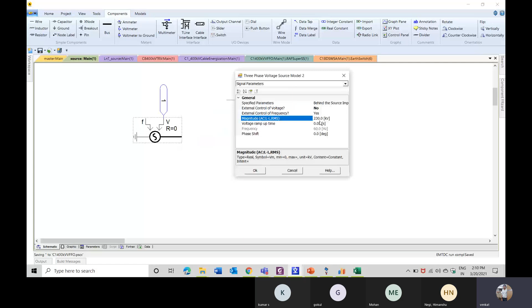Like this, this option varies, and this ramp up time I showed you yesterday. The voltage here is your line to line RMS, which is already your line voltage. For example, if it's 220 kV line or 132 kV, it has mentioned AC line to line RMS, so it is always that. You don't need to change it to another value. For example, you don't need to put 132 kV divided by root 3. It is not required. Whatever is the rated voltage of the system, you can just put that here.